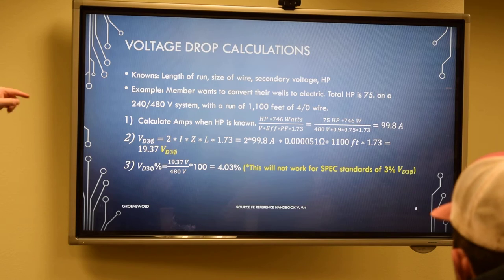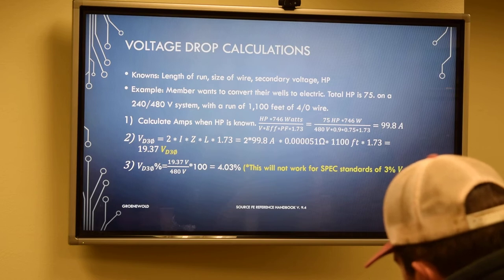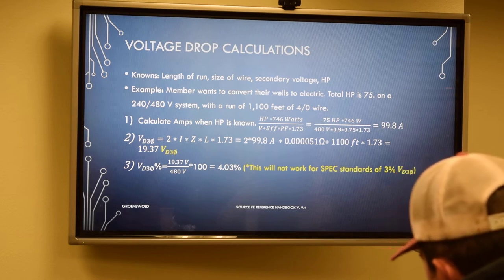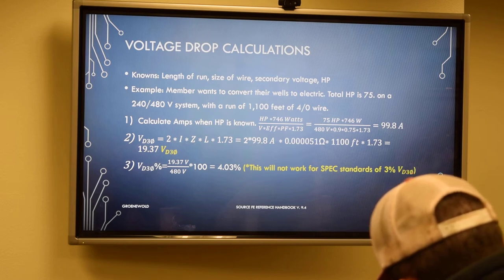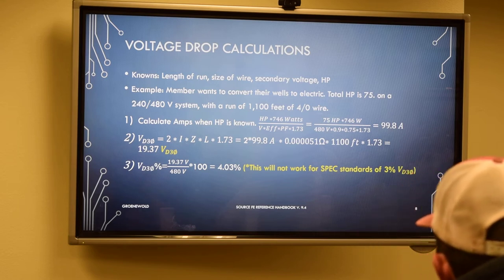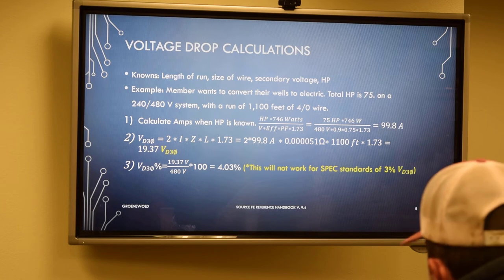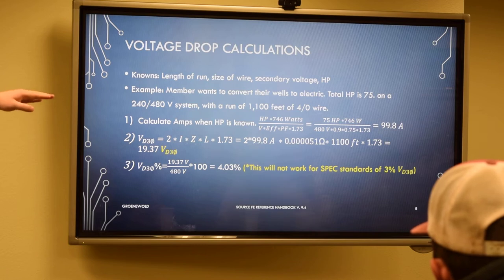You'll divide it by the voltage, which is 480. The efficiency of a motor, we represent that as just 90%, because motors these days are very efficient. When we model it in our Windmill software, we use a power factor of 75 for anything irrigation. The 1.73 comes into play later on as well. I'll touch more on that. That is just the square root three for a three-phase system. So when you do that equation right there, you'll get your 99.8 amps with a known horsepower.